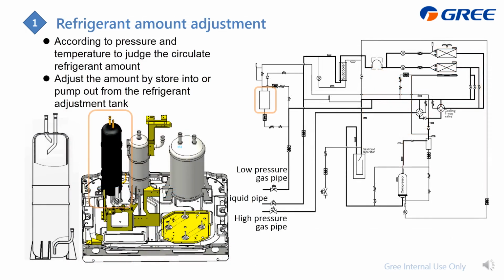For the heat recovery system, as the outdoor unit needs to handle the combination of different indoor unit operating modes, the best refrigerant circulating amount should also be different. So in the outdoor unit, we have this device, which is this one. We call it a refrigerant tank, to adjust the circulating refrigerant amount according to the pressure and the temperature. The system will judge whether it is the best refrigerant amount.